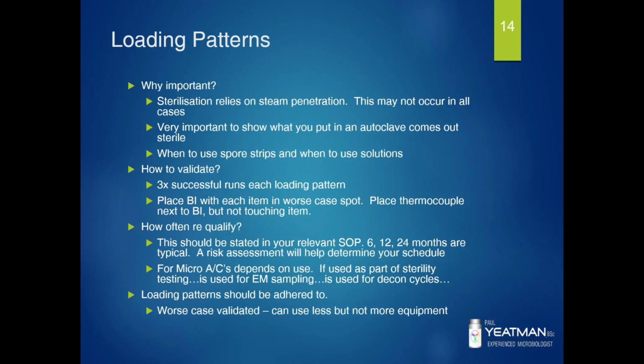One thing you should note here is that when you do your validation runs, the autoclave should be at room temperature, which is the worst case thermal load transfer. So a cold autoclave has to heat up more than an autoclave that is warm. And a cold autoclave may impact the ability of the autoclave cycle to kill off your BIs versus running a cycle immediately after another cycle, for example, when the autoclave is up to room temperature or close to it.